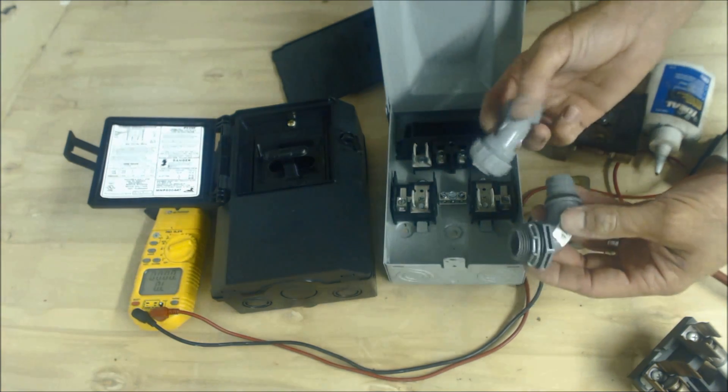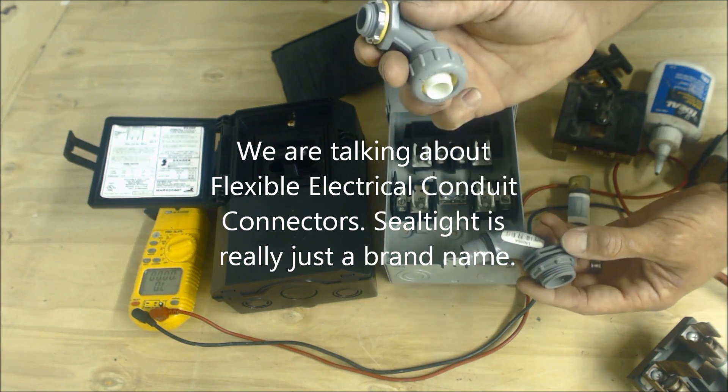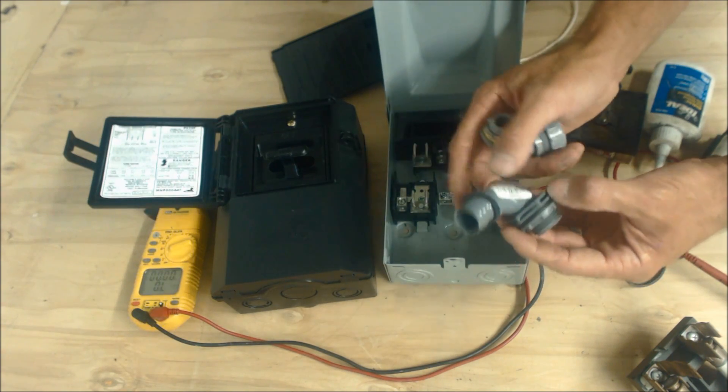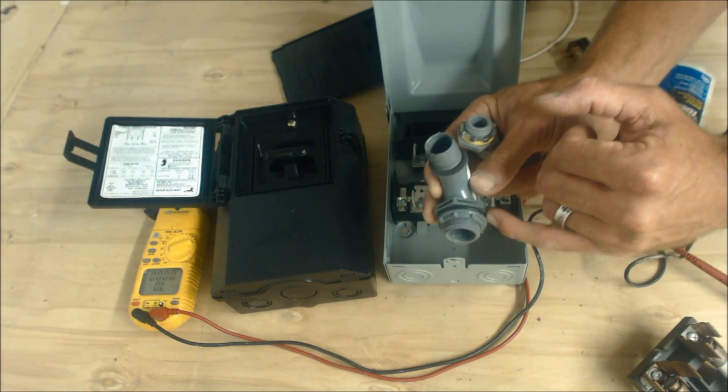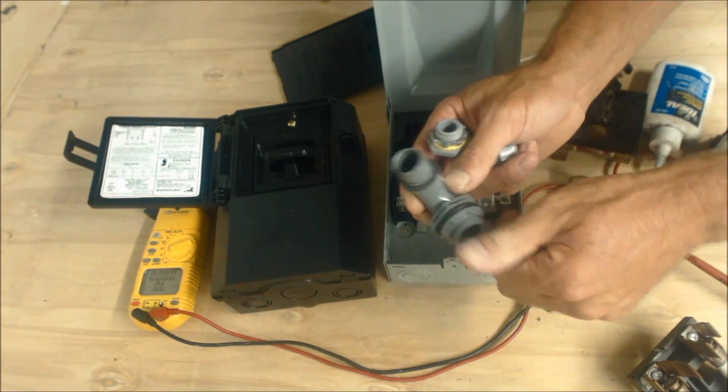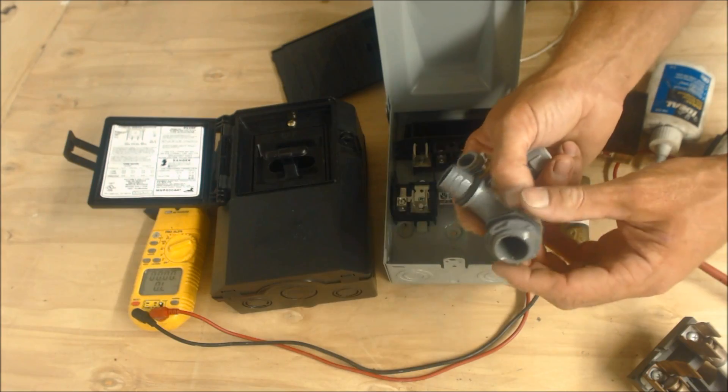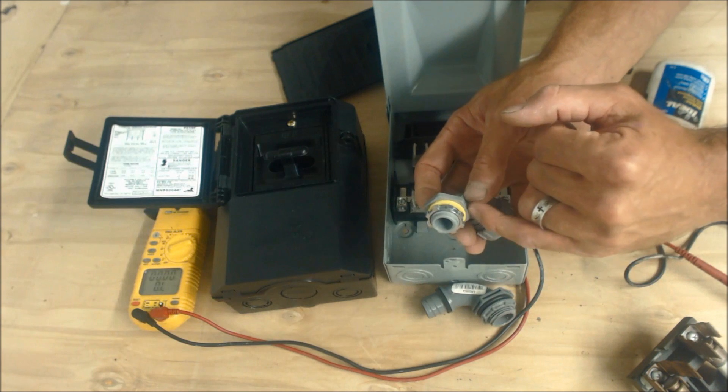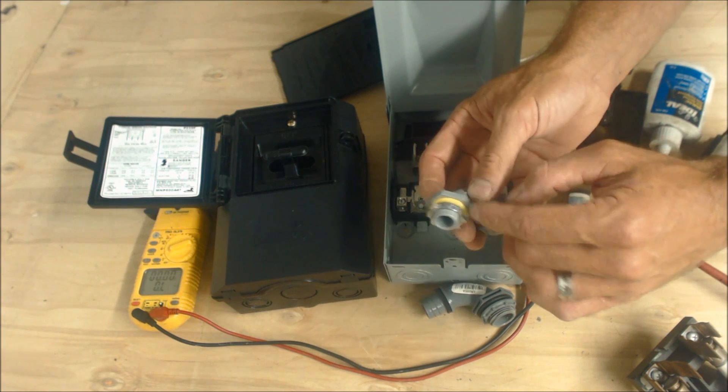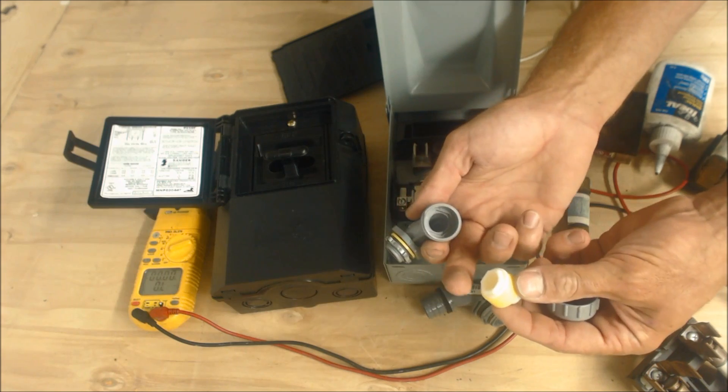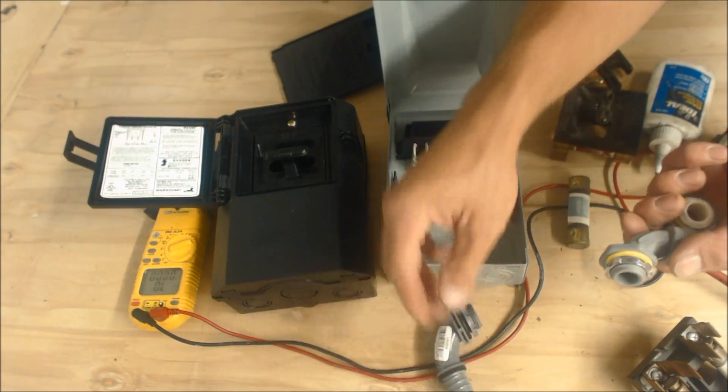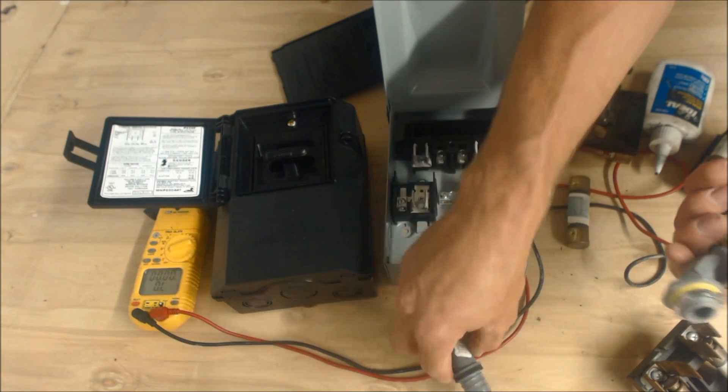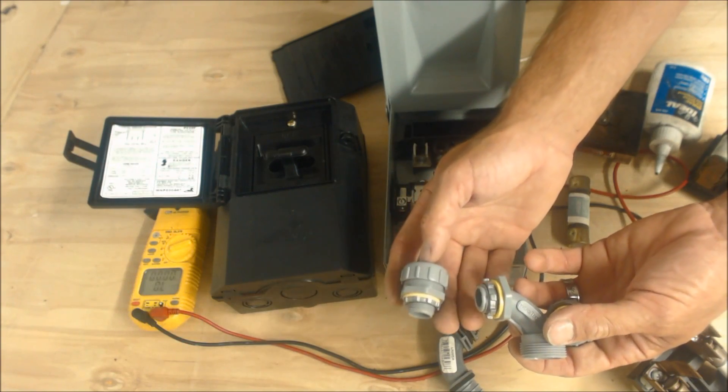Another thing is when you're using your outdoor seal tight right there, what you can do is, I would not recommend this version right here because what happens is you're tightening your seal tight right onto this little foam ring and then you're relying on this rubber gasket. This rubber or rubber washer, a lot of times I've found just cracked just due to old age or broken and not making a good connection. This is just my perspective. So if somebody likes those, I'm just trying to give you my perspective on things. This type of ring holds up a lot better. As well, when you have a seal like this that's multi-part, it's a lot better than just relying on this one piece of foam. So even though this may be quicker and maybe you might find it easier or maybe even cheaper, I would highly recommend a connector such as this, or a straight connector.